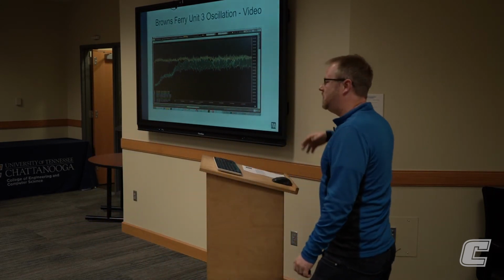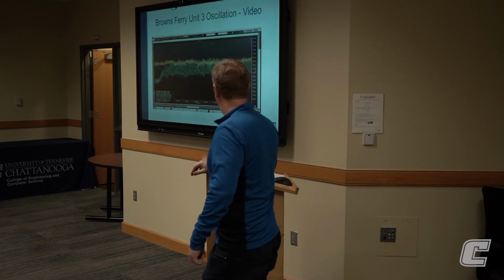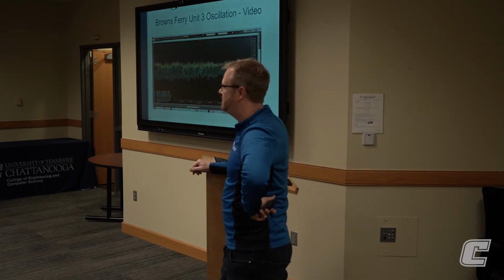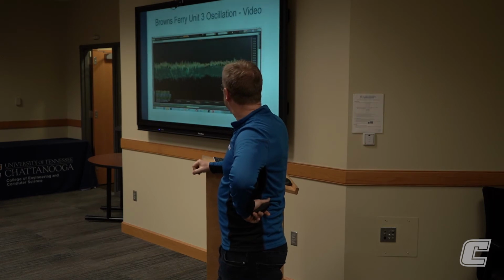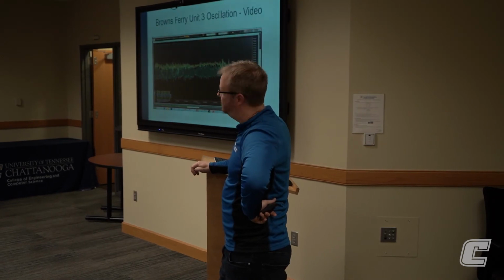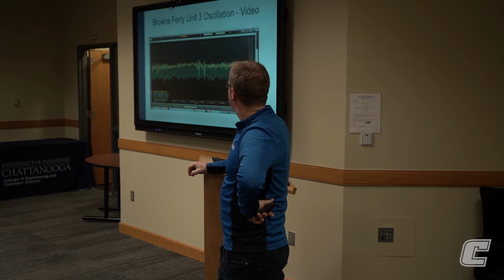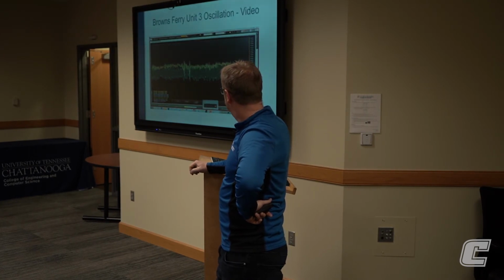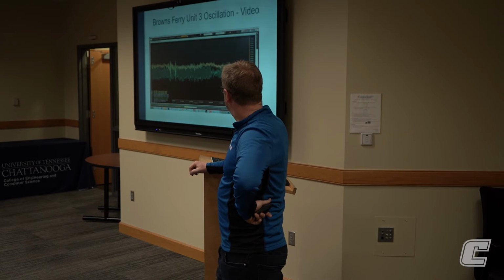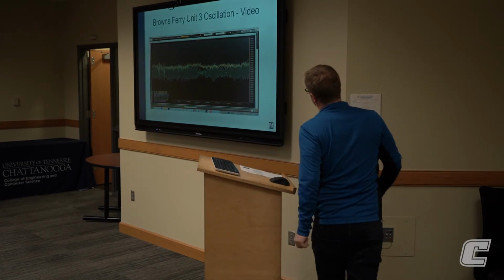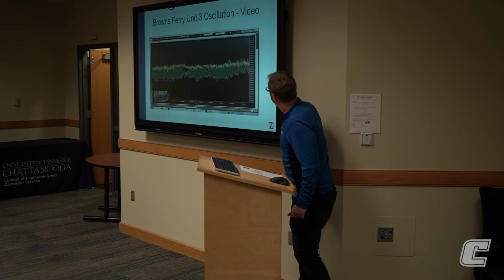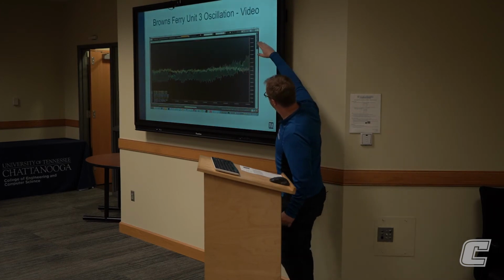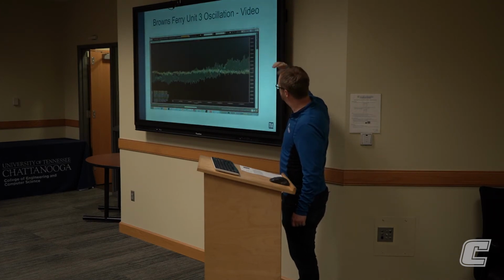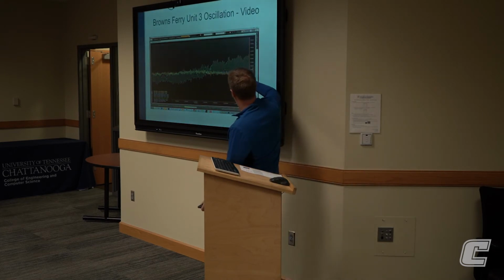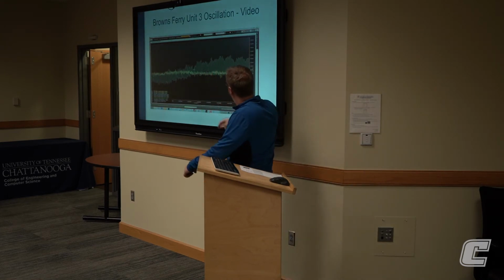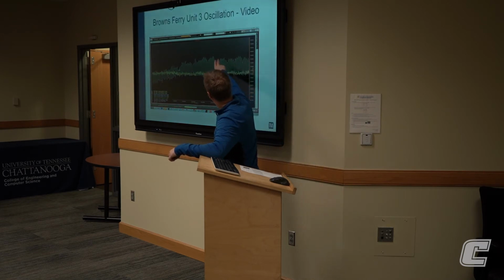So this is what RTDMS, the software we just saw on the previous slide, is alarming to. It's saying there's an oscillation here. You know, what's going on? So we started getting the alarms, as they're bringing the unit up. So we're at a little over 1,100 megawatt output. So they're still bringing the unit up. Remember, its new value is closer to 1,300 now. So it's going to be higher than Unit 2. Now the oscillation is growing even more peak to peak.